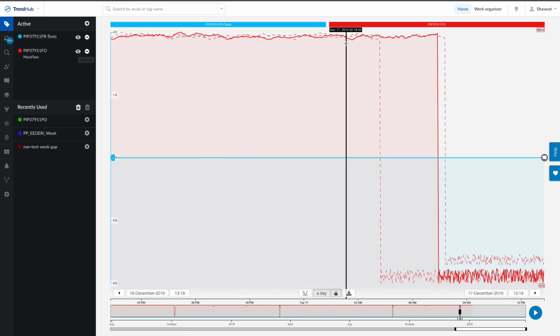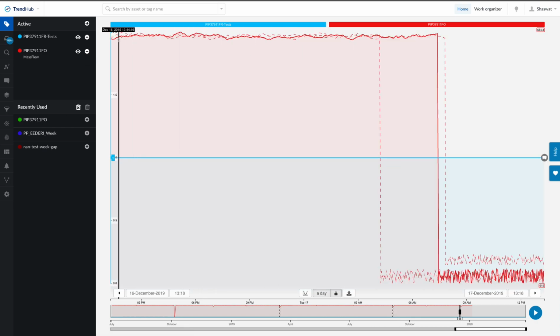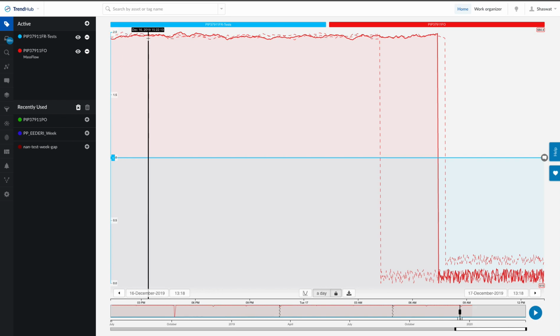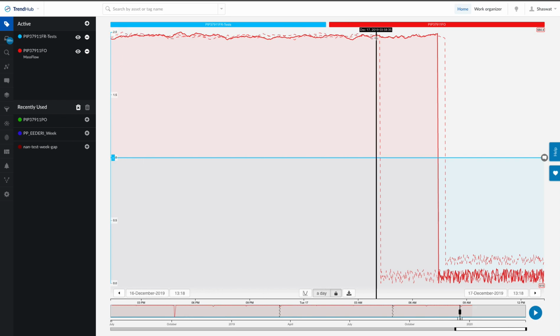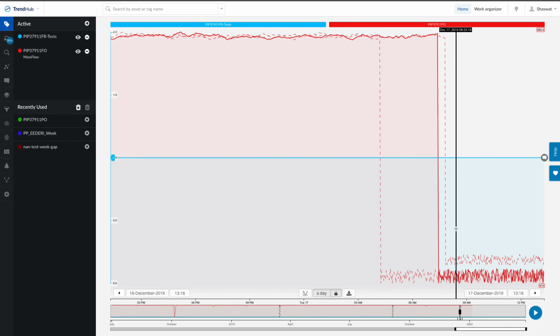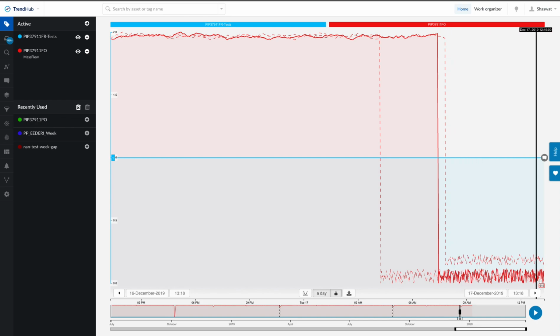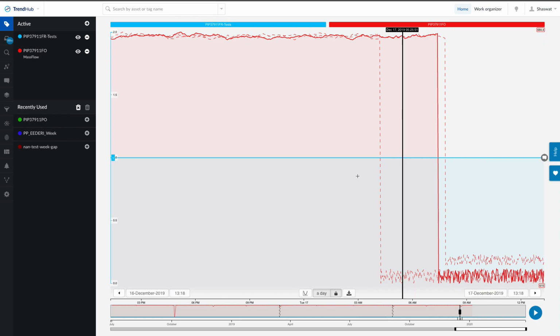As I do that, you can certainly see that we were flowing around 680 and then something happened and flow dropped to around 615, as you can see, 615 or 620 range. So it's a huge drop, and this drop is happening because of the leak, as someone noted here.